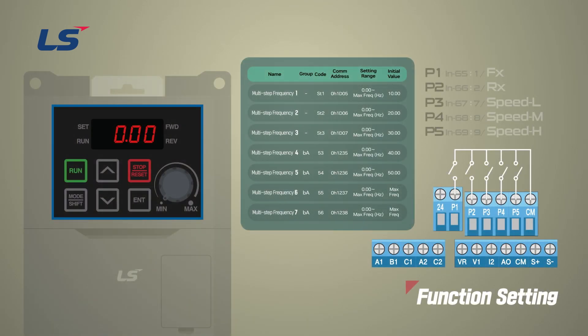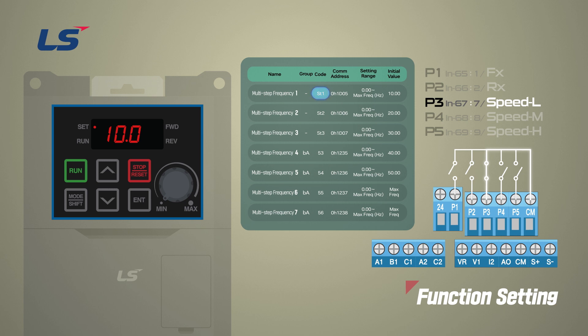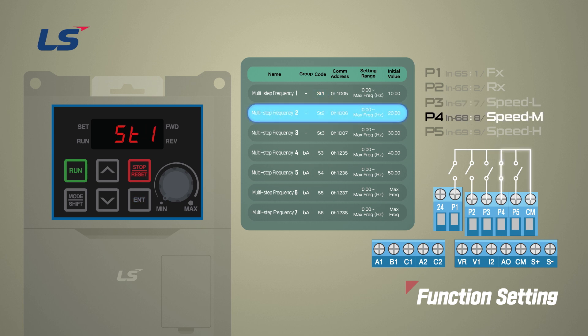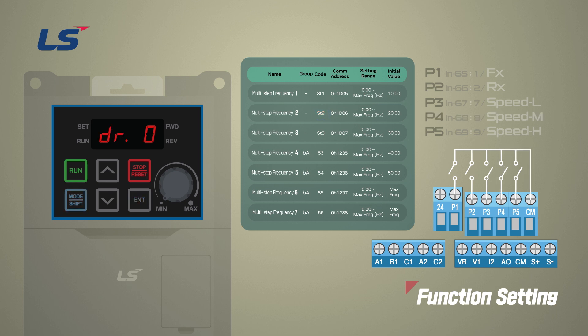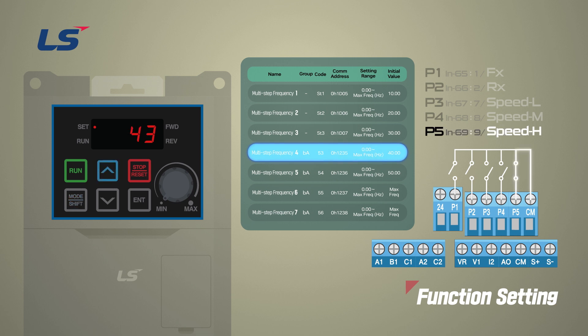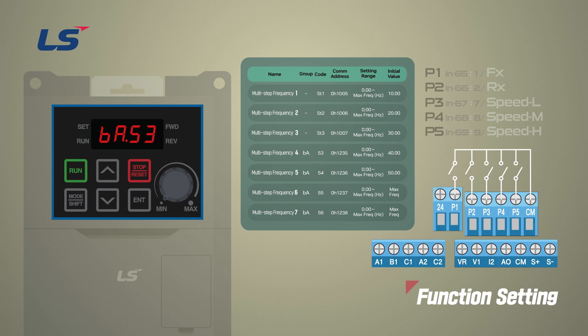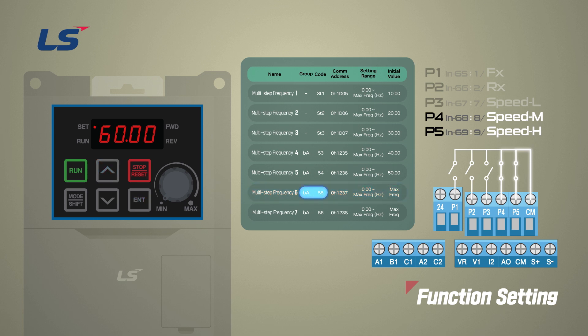The P3 terminal means first stage frequency, and the first stage frequency value is set in operation group ST1, multi-step frequency 1. The P4 terminal means second stage frequency, set in operation group ST2, multi-step frequency 2. If only the P5 terminal is input, it means the fourth frequency, set in B-A53, multi-step frequency 4. If P4 and P5 terminals come on at the same time, it means the sixth stage frequency, set in B-A55, multi-step frequency 6. By this combination, speed settings for each interval can be set up to B-A56, multi-speed frequency 7.